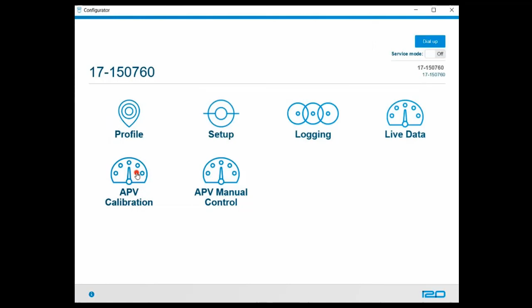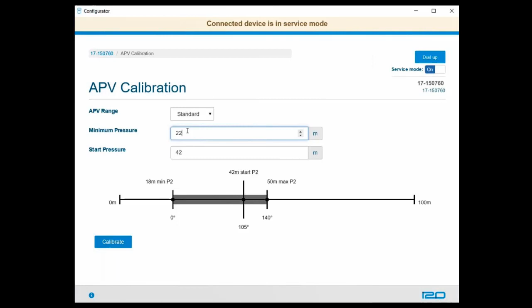Once you're in service mode, you can click and type the minimum P2 that you have fixed manually by adjusting the end cap. The default for this is 18, but in this example we've got 22. We then set the fixed outlet P2 pressure that we want to achieve after calibration. The maximum P2 is set automatically. Once you click the calibrate button, a series of confirmation messages will appear on the main screen. Please read these very carefully before you click OK, because the APV will adjust and we want to make sure that it's safe to do so.